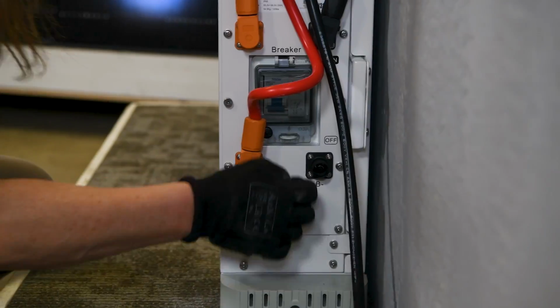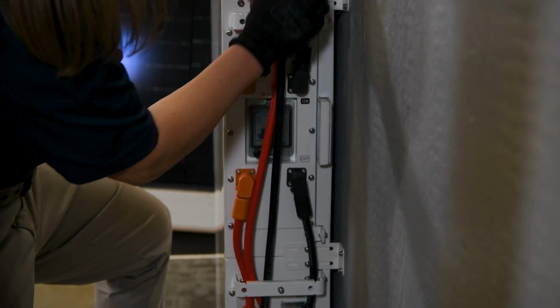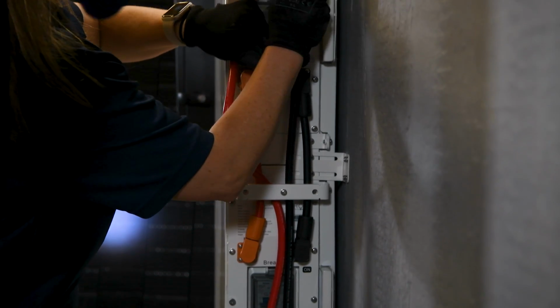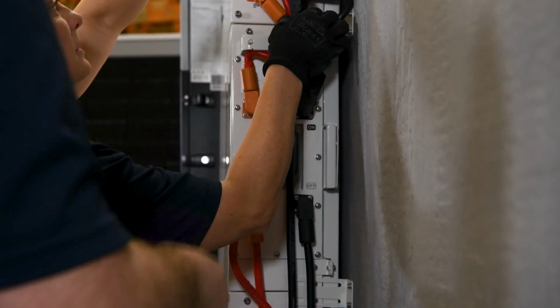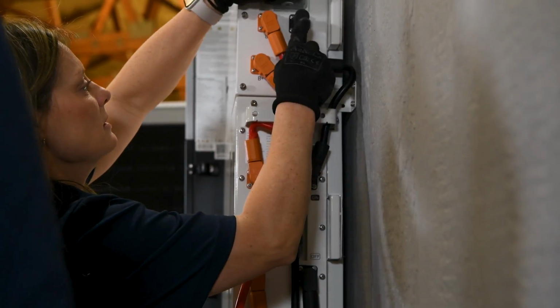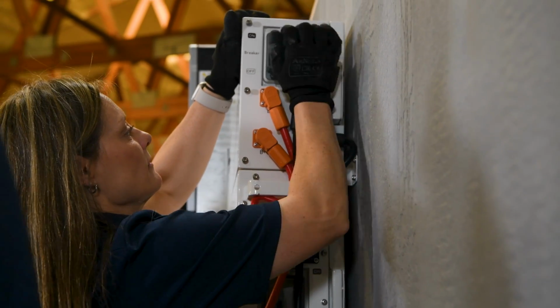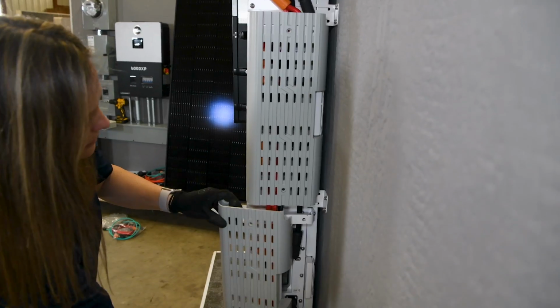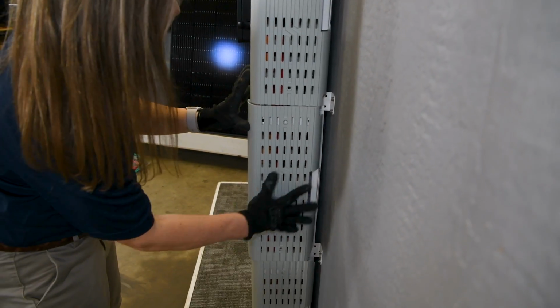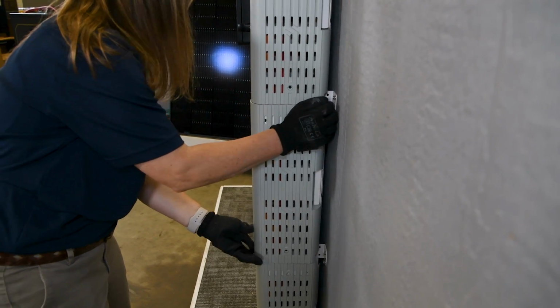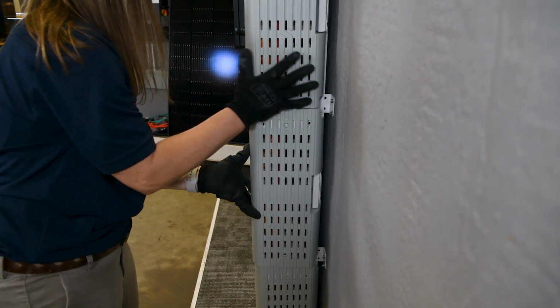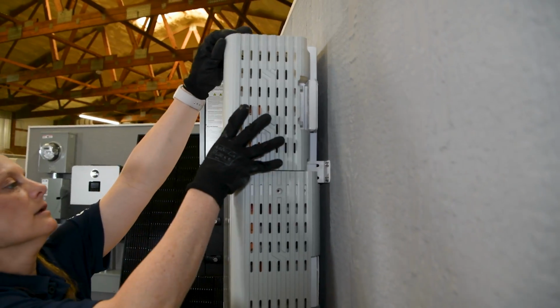the cables. Achieve this by looping the cables back to the top from both sides, carefully routing them under each handle. This technique is effective for both the 10 kilowatt-hour setup with 2 battery modules and the 15 kilowatt-hour configuration with 3 modules. Completing this step allows you to neatly install the covers, presenting a sleek and compact backup system.